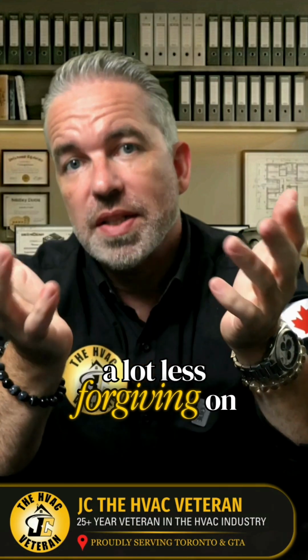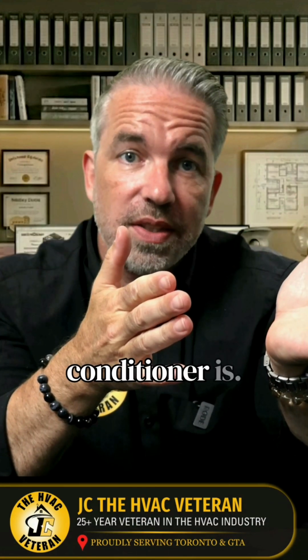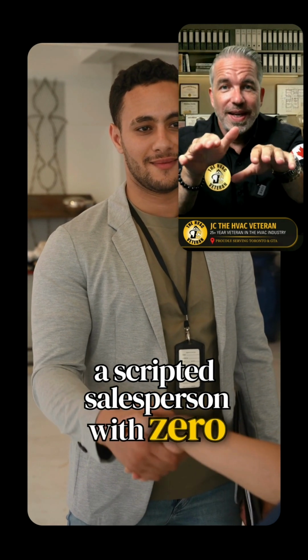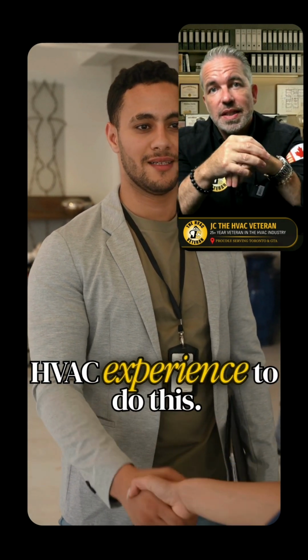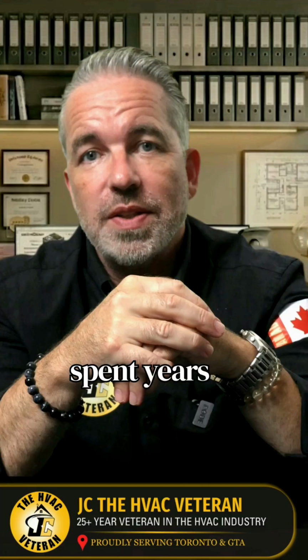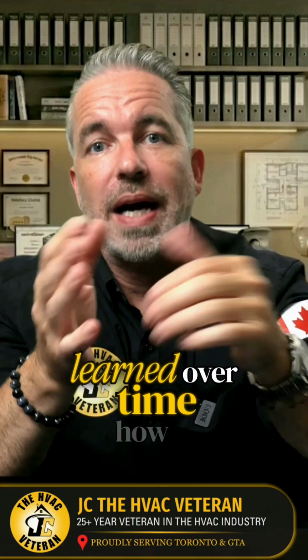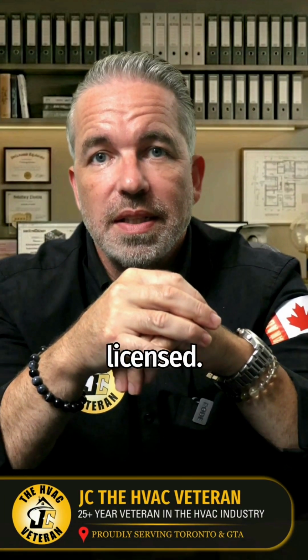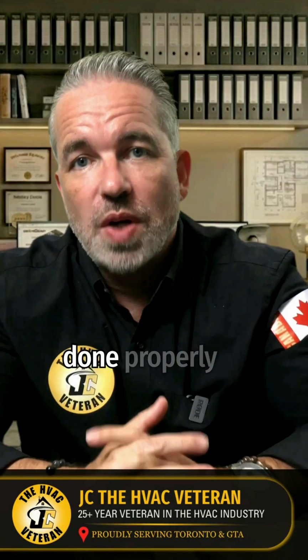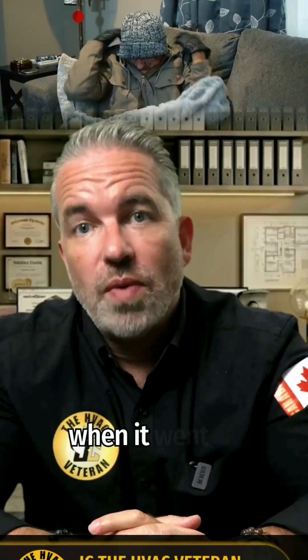Because heat pumps are a lot less forgiving on duct sizing than an air conditioner is, you don't want to trust a scripted salesperson with zero HVAC experience to do this. Trust only those who have spent years in the trenches, learned over time how to do it right, and are licensed. If the load calculation wasn't done properly or at all when it went in, you can experience big airflow problems down the road.